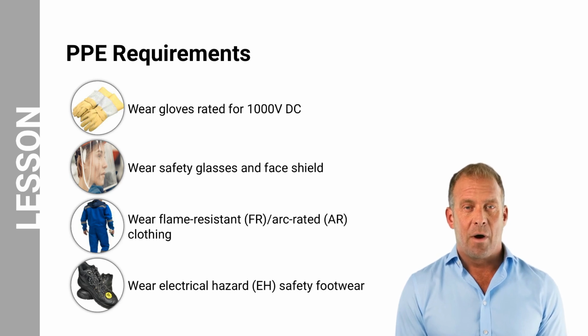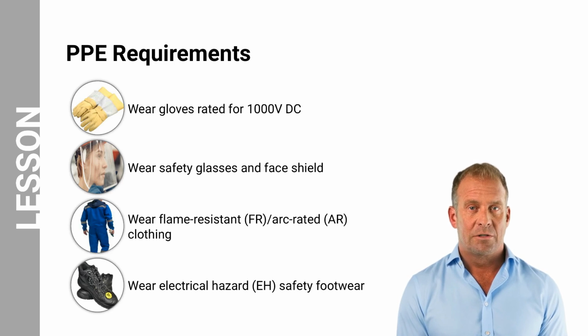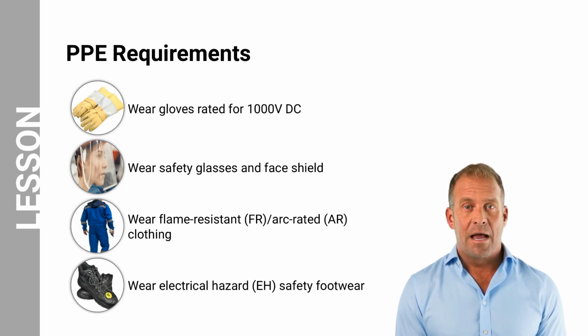Let us now look at the requirements to ensure you are safe. When working on high voltage systems, wearing appropriate personal protective equipment that includes gloves rated for 1,000 volts DC, safety glasses and face shield, flame-resistant and arc-rated clothing, and electrical hazard safety footwear are crucial to ensure the safety of technicians. Safety glasses provide eye protection against potential hazards such as electrical sparks, debris, or chemical splashes. Additionally, a face shield offers an extra layer of protection by covering the entire face, including the eyes, nose, and mouth, from any potential impact or splashes.